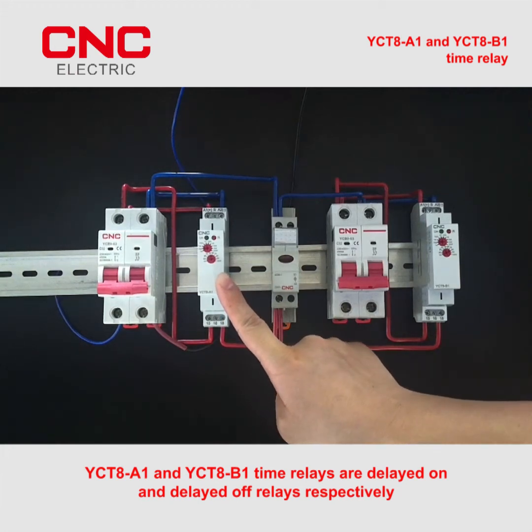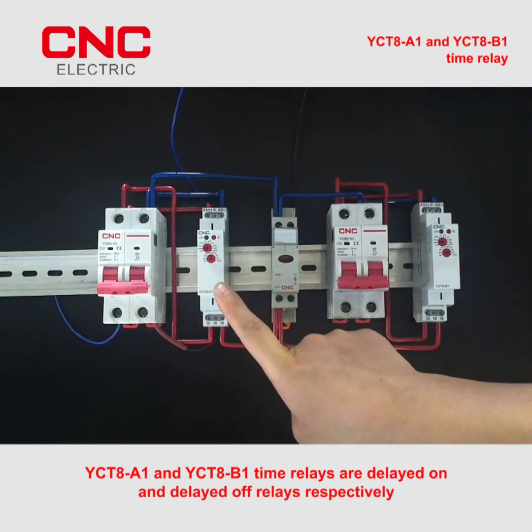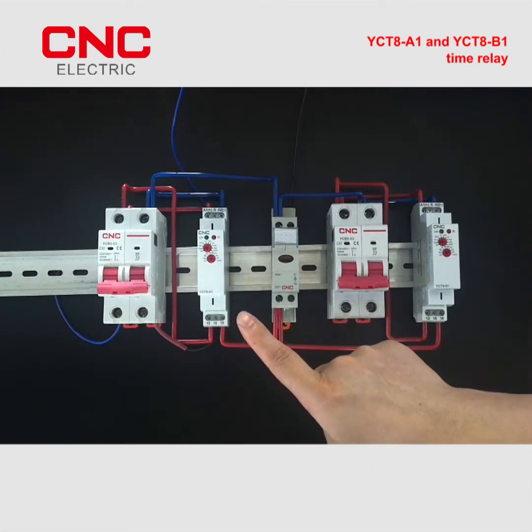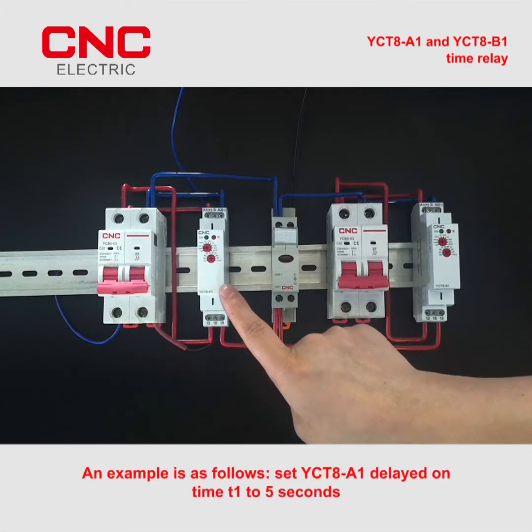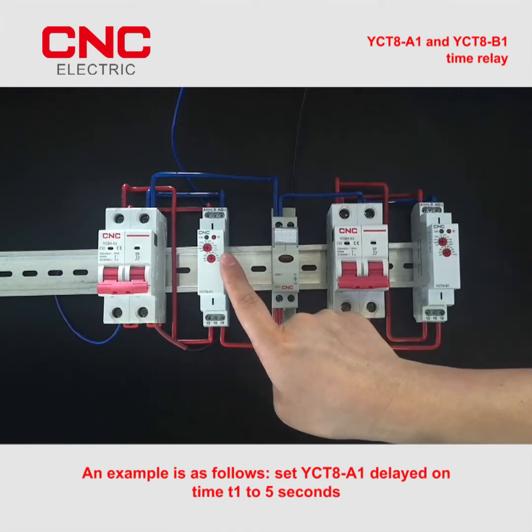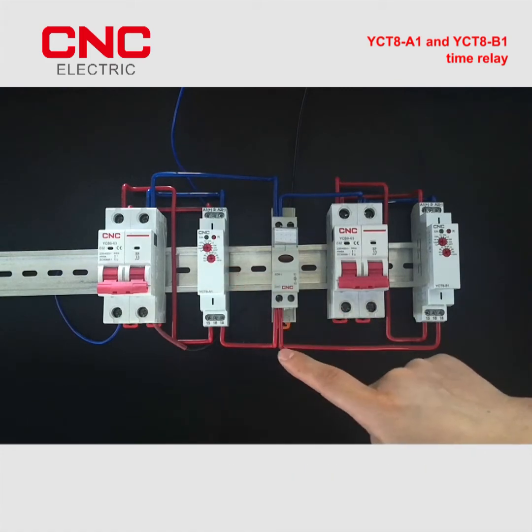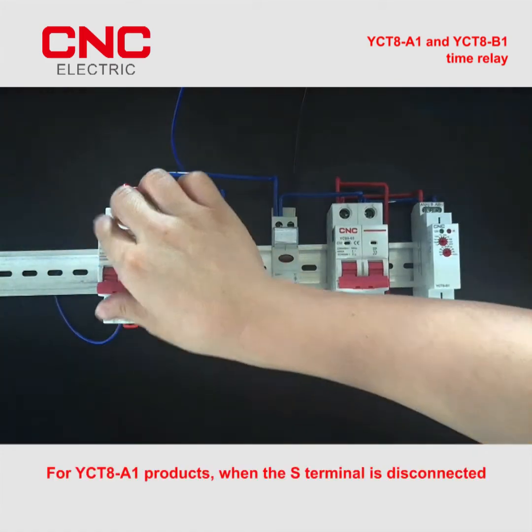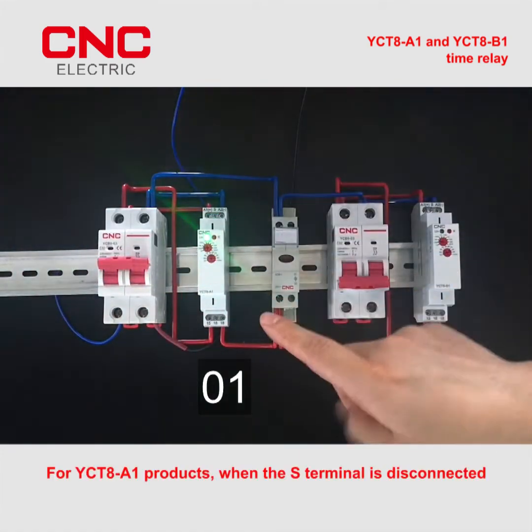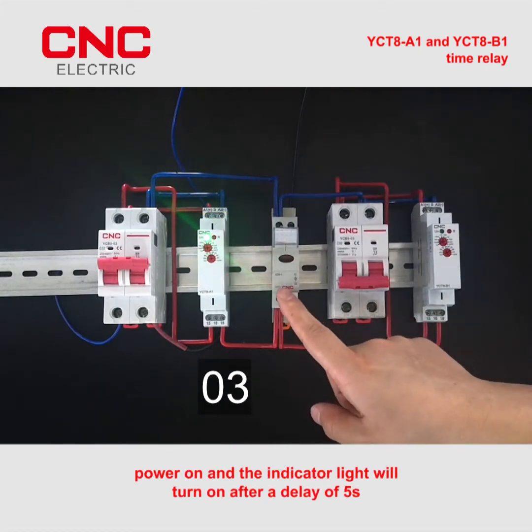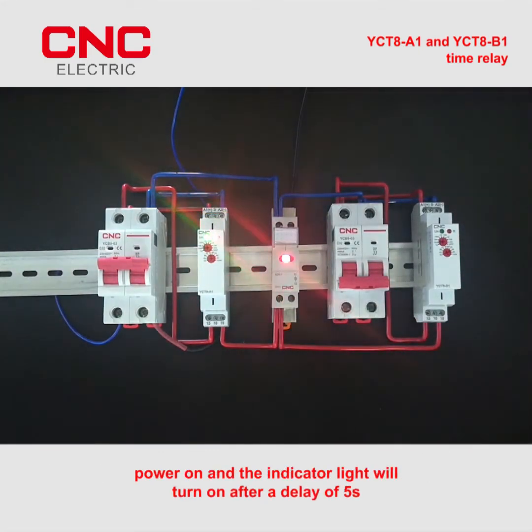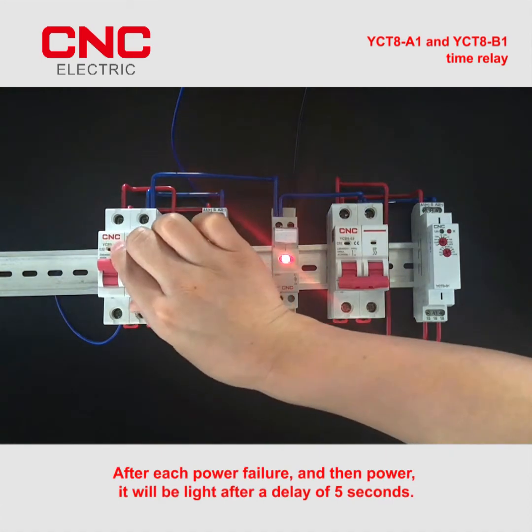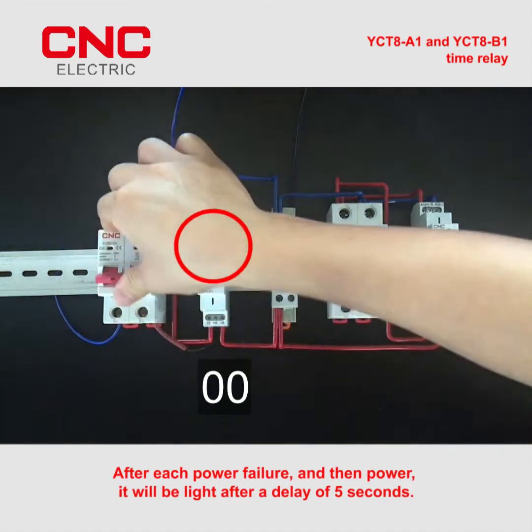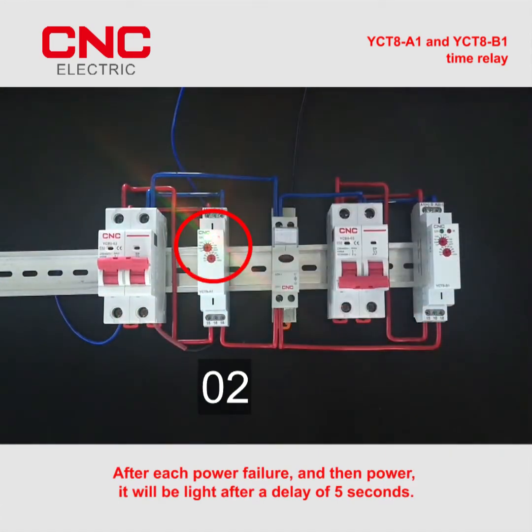YCT8A1 and YCT8B1 time relays are delayed on and delayed off relays respectively. An example is as follows: set YCT8A1 delayed on time T1 to 5 seconds. For YCT8A1 products, when the S terminal is disconnected, power on and the indicator light will turn on after a delay of 5s. After each power failure, and then power, it will be light after a delay of 5 seconds.